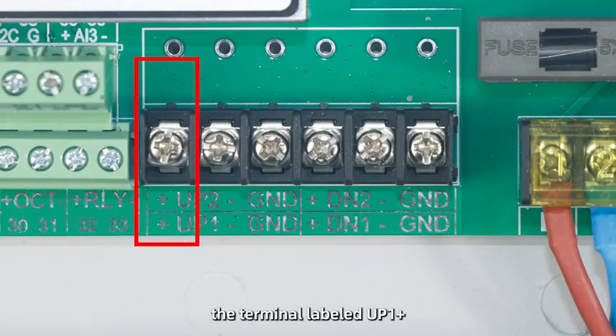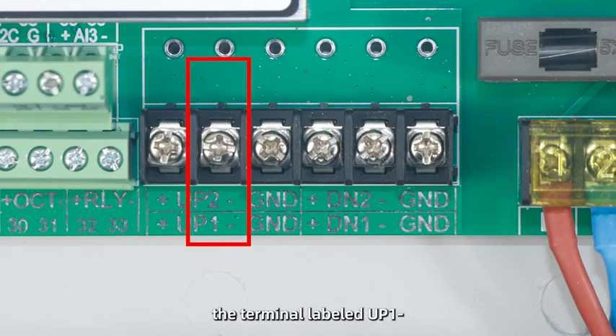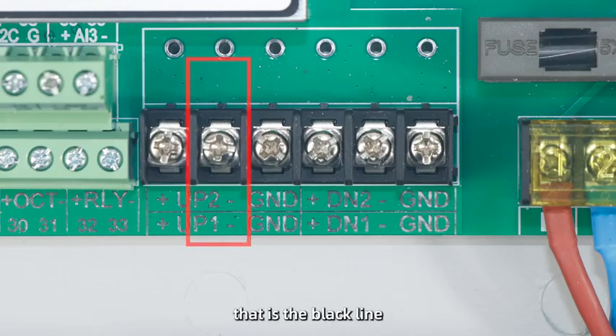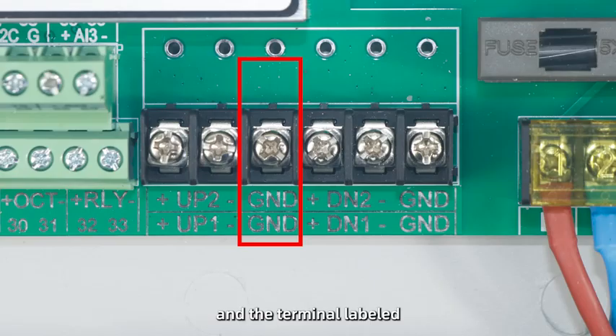The terminal labeled UP1+ is used to connect the positive pole of the upstream probe connecting line, that is, the red line. The terminal labeled UP1- is used to connect the negative pole of the upstream probe connecting line, that is, the black line. And the terminal labeled GND on the left is used to connect the copper-shielded wire of the upstream probe connecting line.